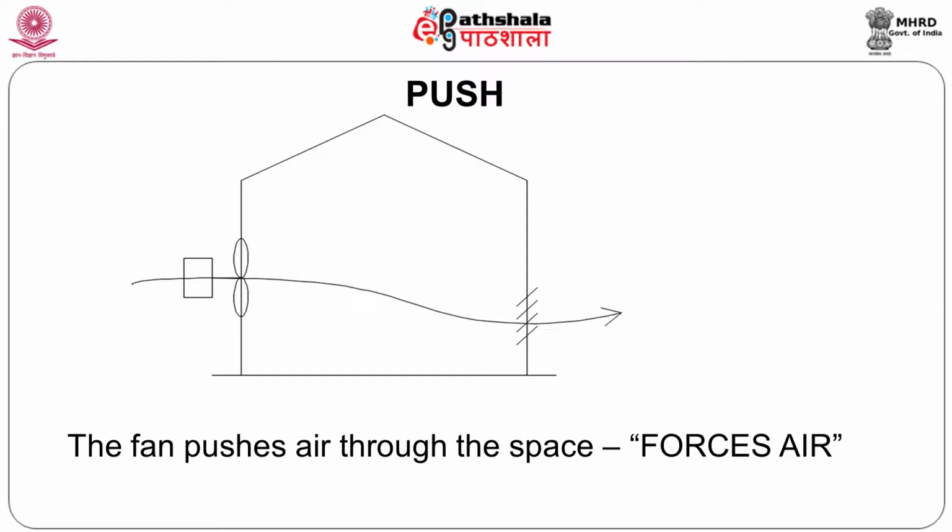Now this kind of ventilation system is ideal for industrial applications because it gives you control on the internal pressures to be maintained. For instance, supposing you are handling an acid laden atmosphere, you would like to keep the place at negative pressure, which means the amount of inlet air will be lower. The air pushed inside will be a little lower than the air pulled outside. That is when you place the place at negative pressure. So, the vitiated atmosphere inside the shed or enclosure does not proliferate outside.